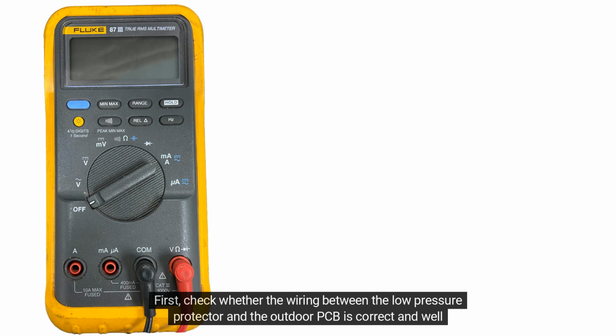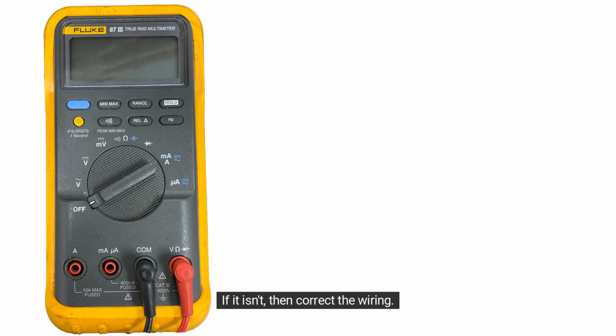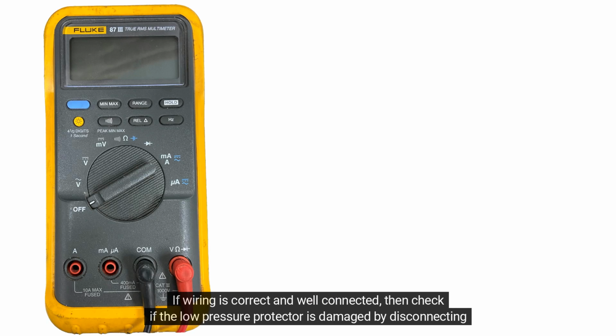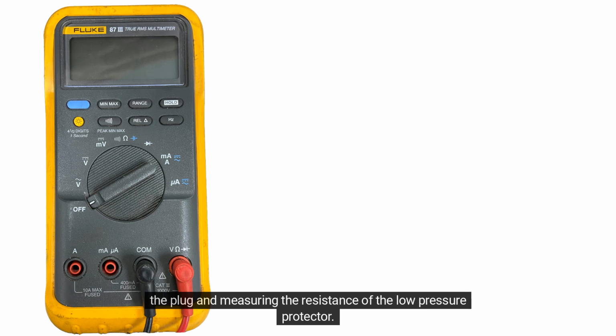First, check whether the wiring between the low pressure protector and the outdoor PCB is correct and well connected. If it isn't, then correct the wiring. If wiring is correct and well connected, then check if the low pressure protector is damaged by disconnecting the plug and measuring the resistance of the low pressure protector. If the protector is normal, the value should be 0. If the value isn't 0, then replace the low pressure protector.